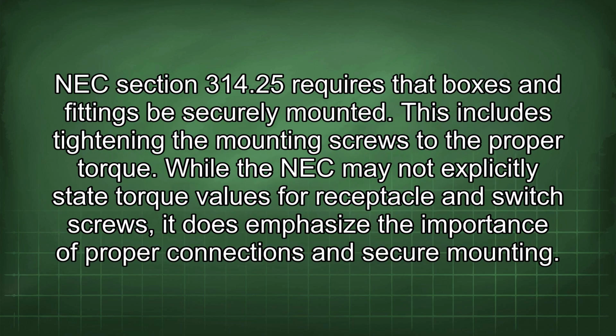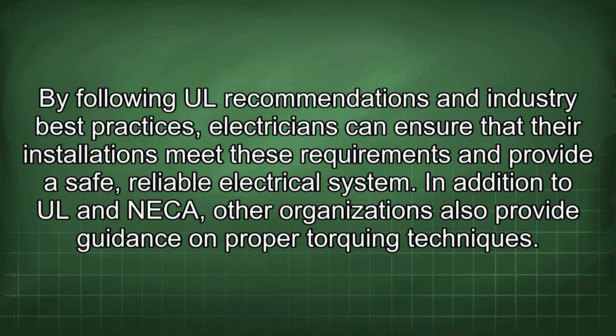NEC Section 314.25 requires that boxes and fittings be securely mounted. This includes tightening the mounting screws to the proper torque. While the NEC may not explicitly state torque values for receptacle and switch screws, it does emphasize the importance of proper connections and secure mounting. By following UL recommendations and industry best practices, electricians can ensure that their installations meet these requirements and provide a safe, reliable electrical system.